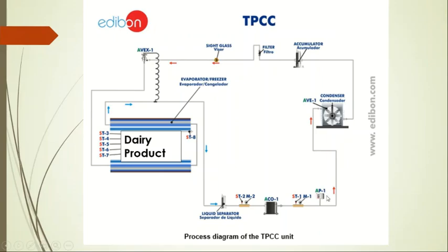The maximum pressure we will allow here won't exceed 250 psi. So if your process runs in a manner that the discharge pressure becomes greater than 250 psi, it will ultimately shut down this complete unit, like condenser, fan, compressor, immediately.